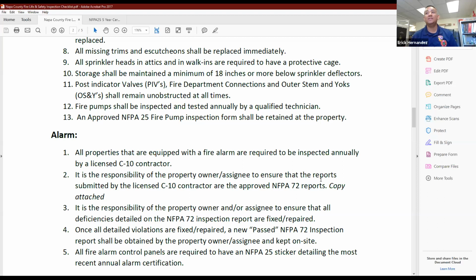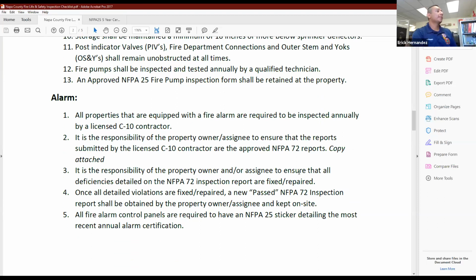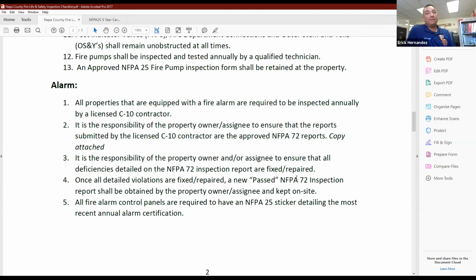That would help reduce the cost, but you have to go through a process. That person has to be certified through the state, has to go through certain classes through the state. And once they obtain a certain permit, then they would be able to do the churn test for you. Okay. If you have a fire alarm system, so if you have a sprinkler system, automatically you would have a fire alarm system. So all alarm systems are required to be maintained by a licensed C10 contractor. Again, it is the responsibility of the property owner to ensure that the reports submitted by the C10 contractor are the approved NFPA 72 reports.